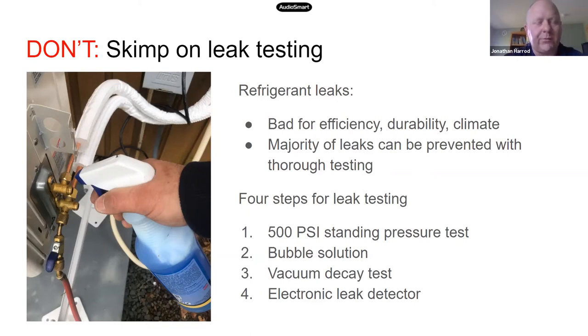Some manufacturers will recommend a 24-hour test. We've concluded that the test can be much shorter as long as you apply this bubble solution, which is what I'm doing here, to all the joints in the system. Check to make sure that no bubbles are forming, which would happen if that nitrogen was leaking out through the flares.